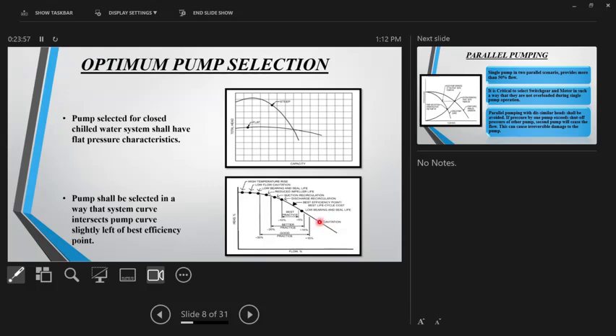So what's really the best point to select? On this curve, there will always be a best efficiency point. AECOM says of that best efficiency point, you try to go plus 5% on the x-axis, meaning in terms of flow, and minus 10%. So if you could select the pump in this region, that's the best practice as far as AECOM is concerned. Again, I'll repeat, there will always be a best efficiency point on a given curve, at a given speed. At the most, plus 5% and minus 10% on the x-axis.